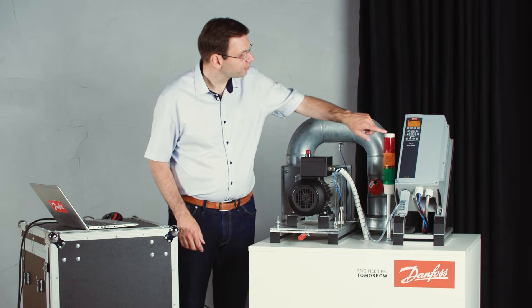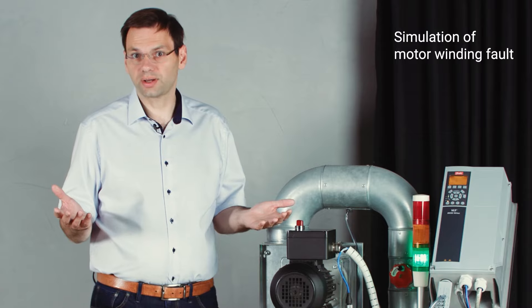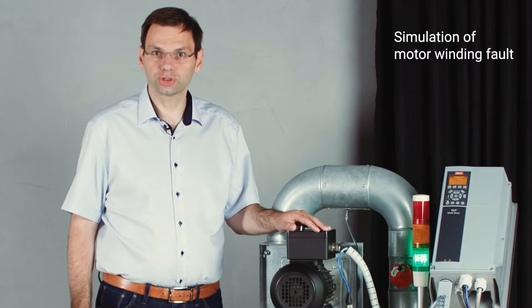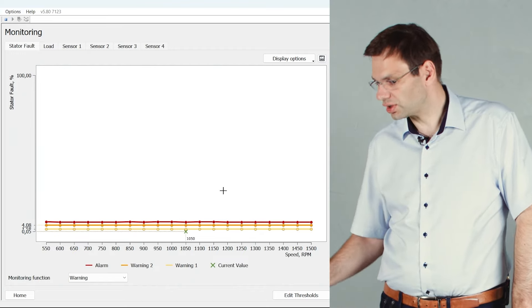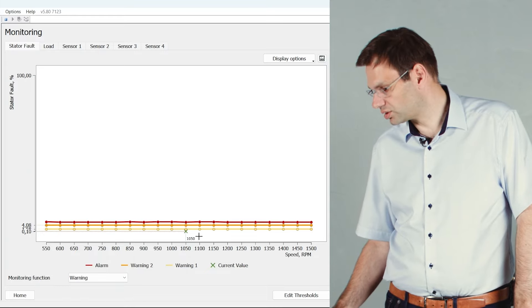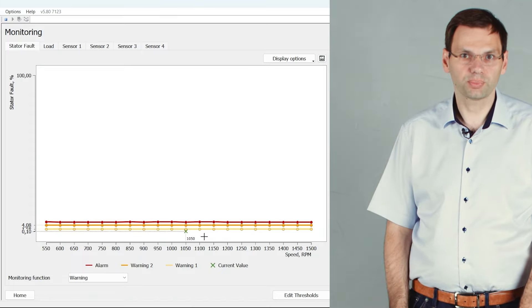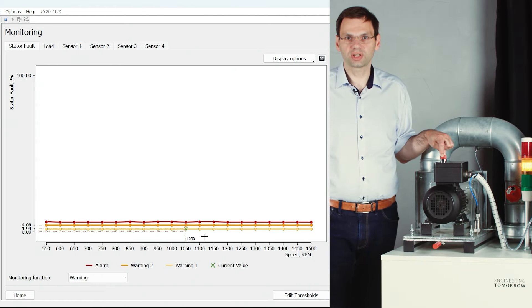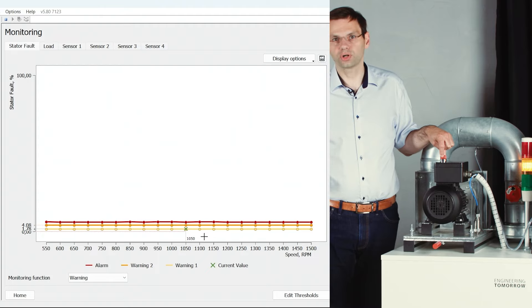First, I will turn on the drive. The motor starts turning and air is coming out. I will now simulate a fault in the motor winding — a turn-to-turn fault. On my PC you can see a graphical representation of the thresholds, with the actual value shown as a green cross. I'm running at 1050 RPM and now I create the turn-to-turn fault. The fault is increasing and the lamp turns orange — I have a warning signal.